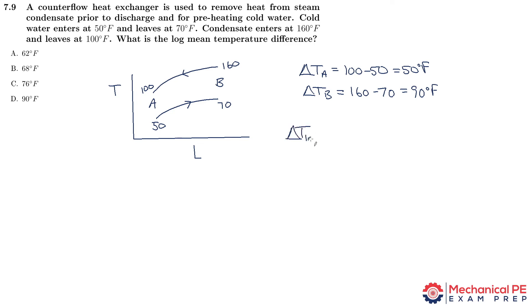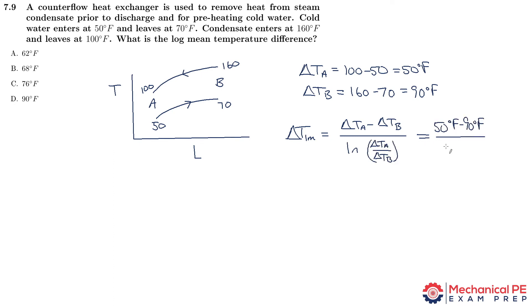Delta T_lm equals (delta T_a minus delta T_b) divided by the natural log of (delta T_a / delta T_b), which is (50 minus 90) divided by the natural log of (50/90). You might notice the numerator is a negative number, but when you take the natural log of a fraction less than one, that also turns out to be negative. So the negatives cancel, and you get a log mean temperature difference of 68 degrees.